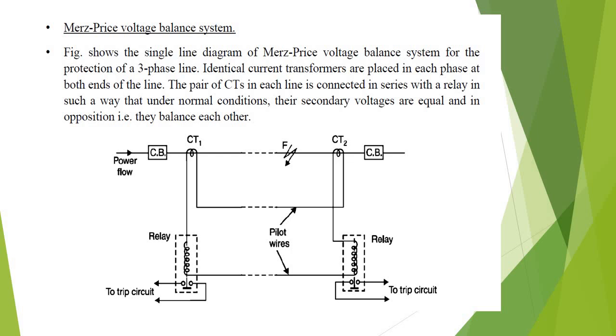Under healthy conditions, the current entering the line at one end is equal to that leaving at the other end. Therefore, equal and opposite voltages are induced in the secondaries of the CTs at both ends, and as a result, no current flows through the relay.